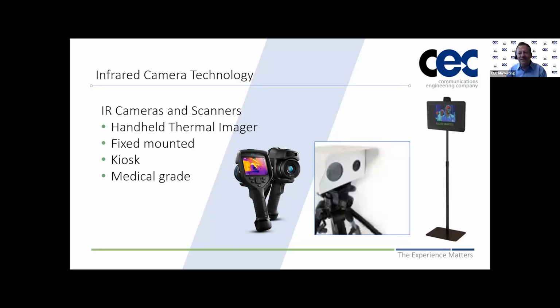But I could see that gaining steam, especially because in high volume situations where you've got to put a lot of people through an area, this might be a way to go and to be able to afford multiple stations, knowing, of course, that you're going to have a little bit less accuracy. As a matter of fact, the accuracy on these are more in the 1 degree. So these could vary by 1 degree plus or minus. So you have to weigh the fact, is that good enough? Knowing that you're going to have more false positives in a situation like that. So, something to consider.